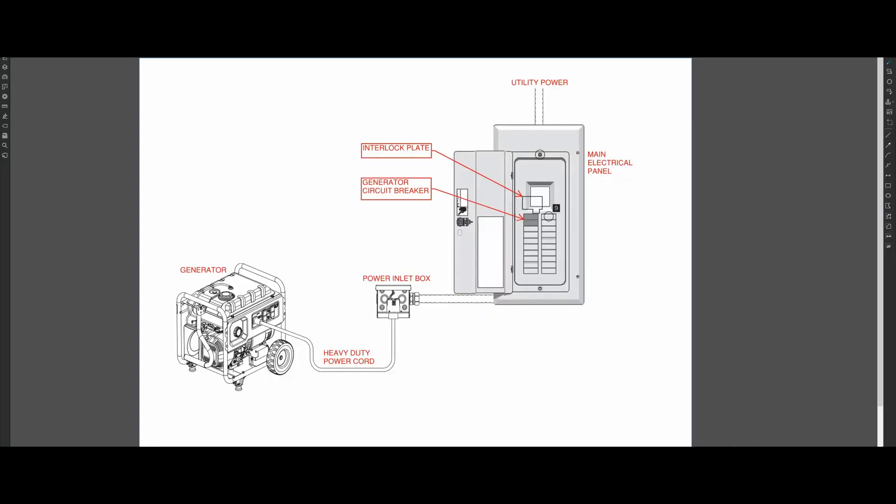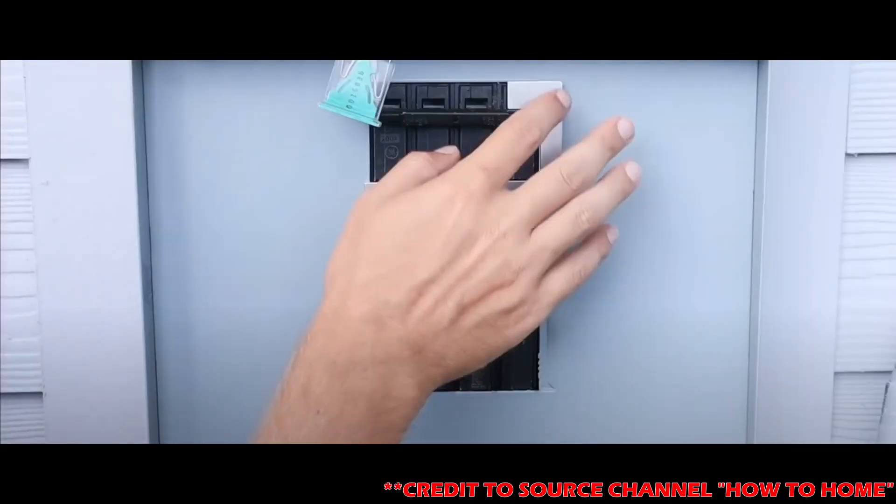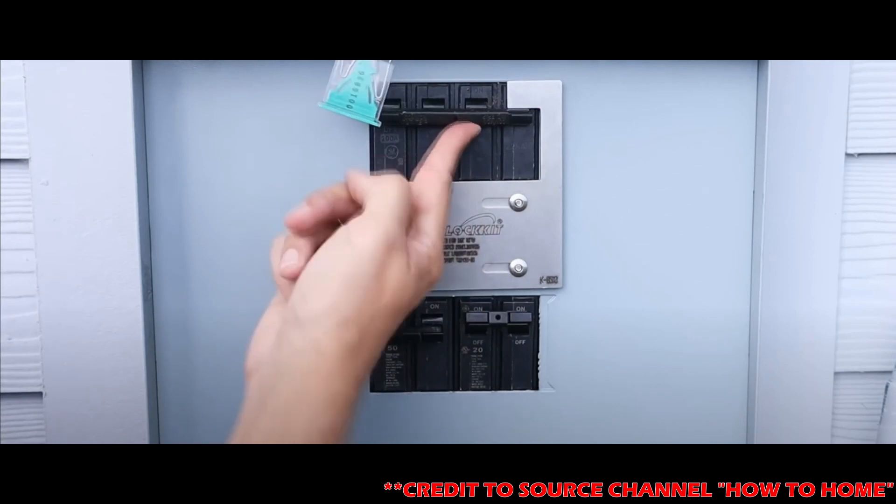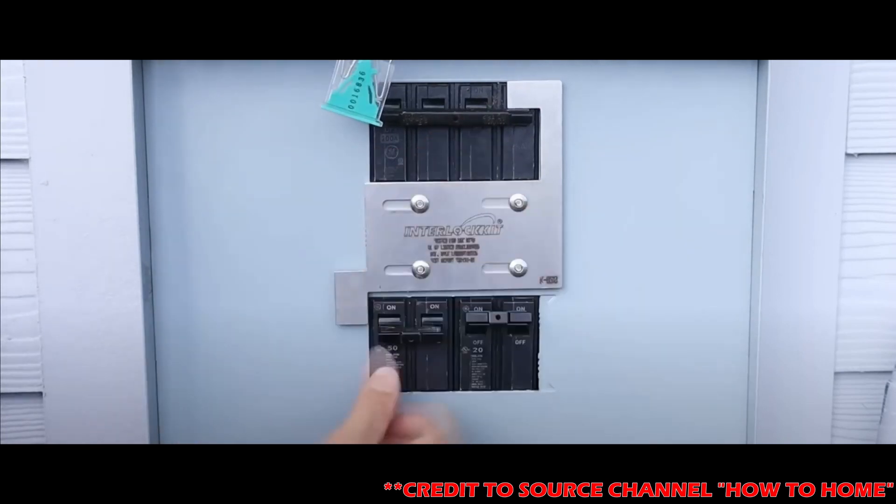An interlock kit system looks like this. There is a power inlet box installed next to your panel that allows you to connect your generator to your panel using a heavy-duty power cord. This is either a 30 amp or 50 amp cord. There is also a metal plate installed over your main panel that prohibits you from running two power sources simultaneously.